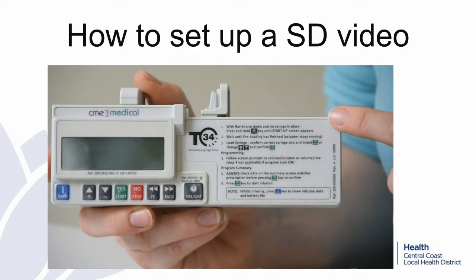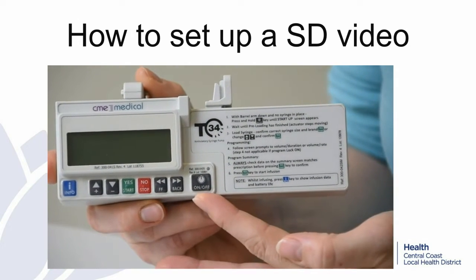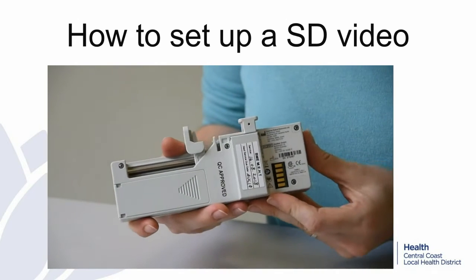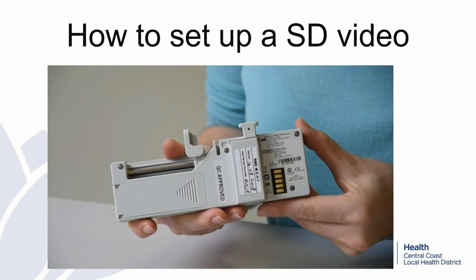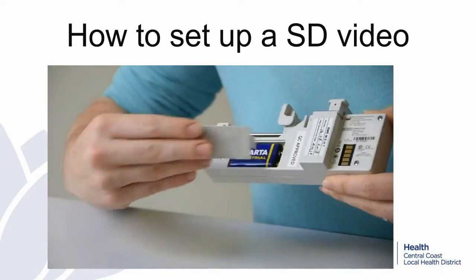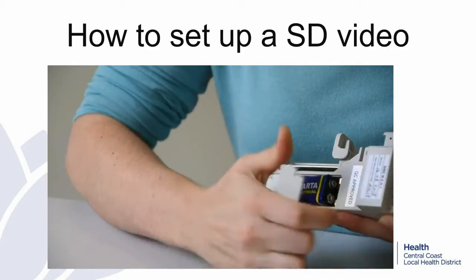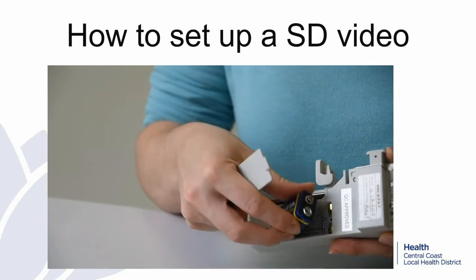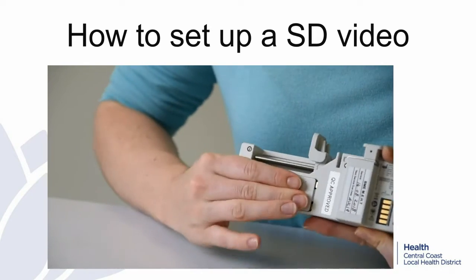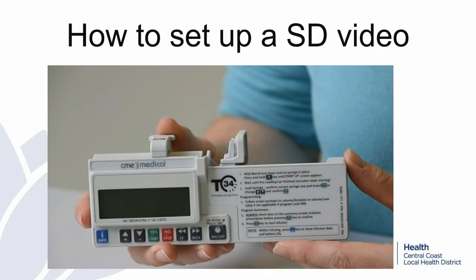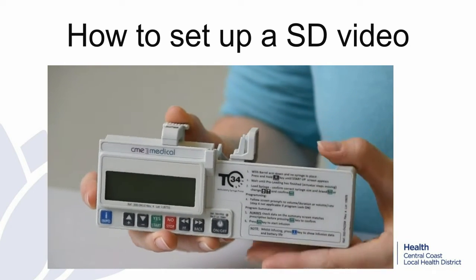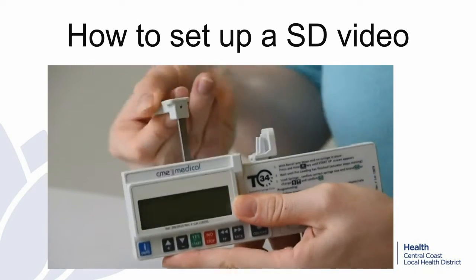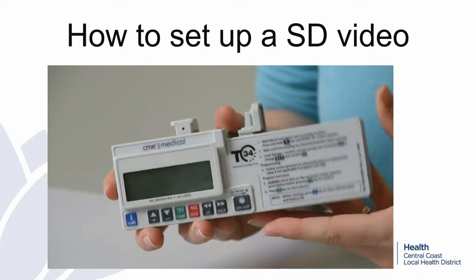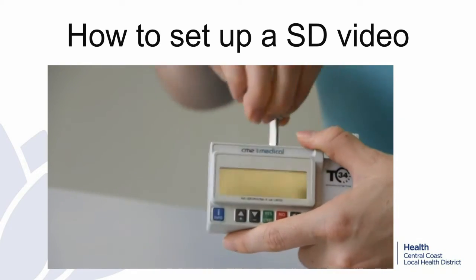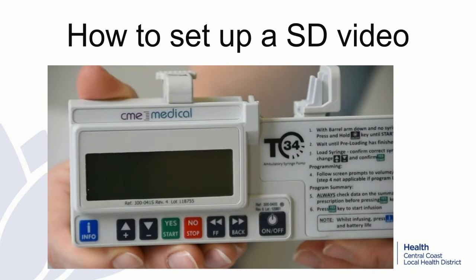How to set up. There are instructions on how to use the pump on the front. You will find the buttons here along the bottom. At the back you will find the serial number. You will also find the battery, open and close like so. This is a computer, so please be careful not to drop or damage the pump. There are 3 detection points: the plunger, collar and barrel clamp arm. Inspect the syringe pump, ensuring it is clean, undamaged, and the barrel clamp arm is down and battery secure.